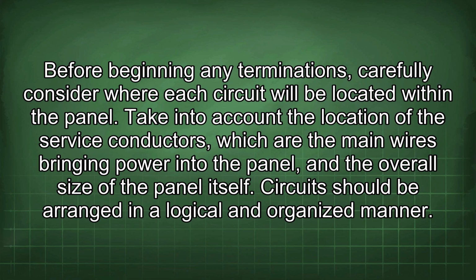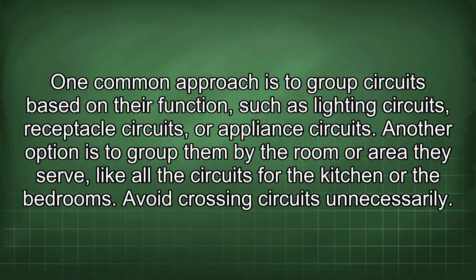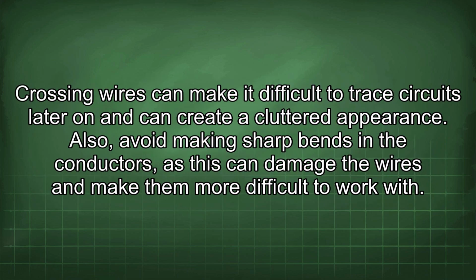Circuits should be arranged in a logical and organized manner. One common approach is to group circuits based on their function, such as lighting circuits, receptacle circuits, or appliance circuits. Another option is to group them by the room or area they serve, like all the circuits for the kitchen or the bedrooms. Avoid crossing circuits unnecessarily. Crossing wires can make it difficult to trace circuits later on and can create a cluttered appearance.